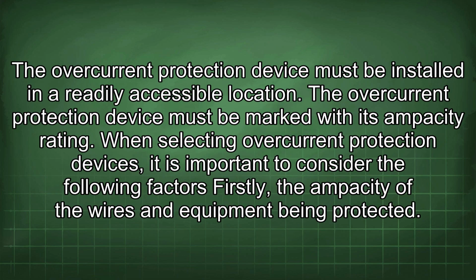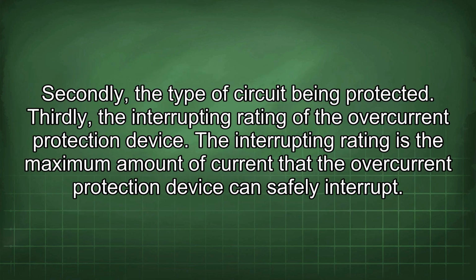The overcurrent protection device must be installed in a readily accessible location. The overcurrent protection device must be marked with its ampacity rating. When selecting overcurrent protection devices, it is important to consider the following factors. Firstly, the ampacity of the wires and equipment being protected. Secondly, the type of circuit being protected. Thirdly, the interrupting rating of the overcurrent protection device.